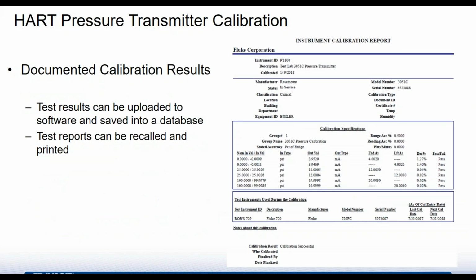Here's an example of a test report. Now this was printed out using Fluke's DPC Track 2 software. You can see in that report you have your company information up on top, the instrument ID, when the calibration was done, information about the device, but more importantly, inside the box, this big box here, this is where those calibration results are stored. And this is what the auditor looks at. So you have your as found, as left results, whether or not the calibration was in specification, and whether it passed or failed.